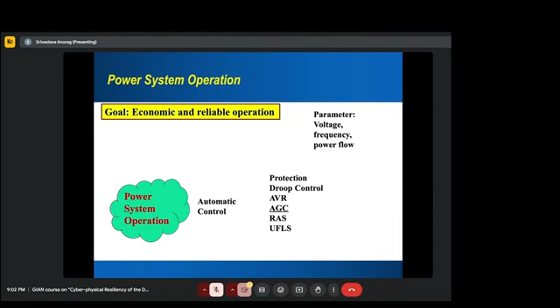A little bit more about AGC. AGC is the online computational tool which we use to control the generation in automatic control by looking at the frequency and also the net tie line interchange. Net tie line interchange is between two different areas, and it looks at how much was planned from this control area, which is one of the areas in the power grid that we decide on the boundary line. Typically, you can think of it like a state. So one state is tied with another state, or one interconnection is tied with another interconnection.